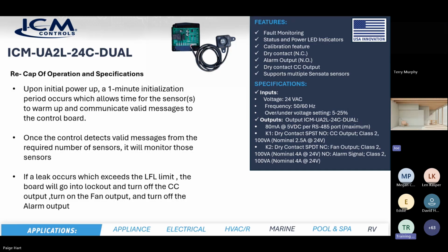Then we have another one. Is it legal to retrofit an existing non-A2L system with a condenser metering device and this mitigation? So I'm not prepared to answer a legal question, but the whole purpose of this board is for that purpose. So yes, it's meant to replace, if you are changing out an A coil, let's say, and there is no mitigation system, and you now have to use A2L refrigerants, then this board is designed for that application.